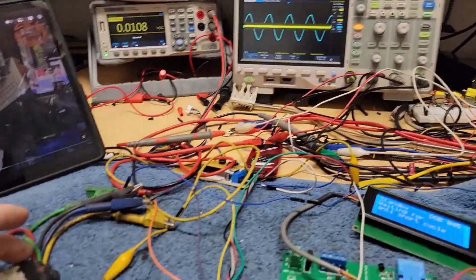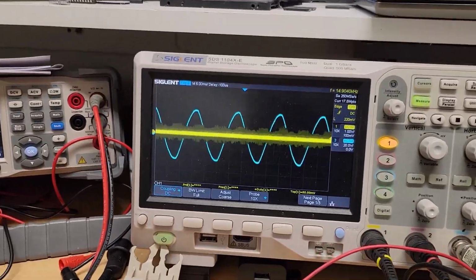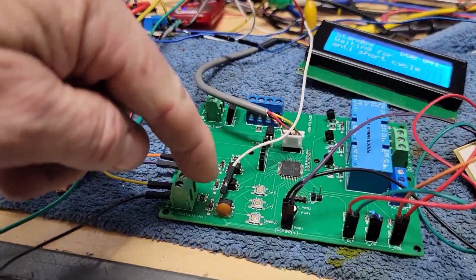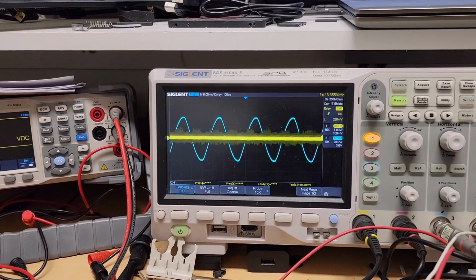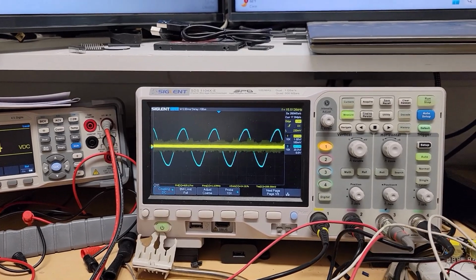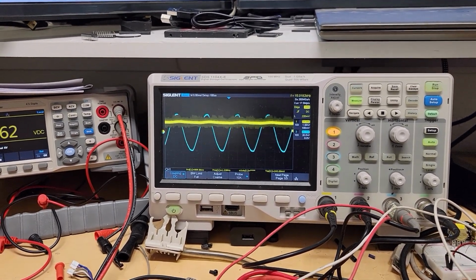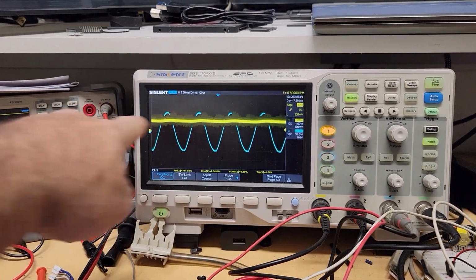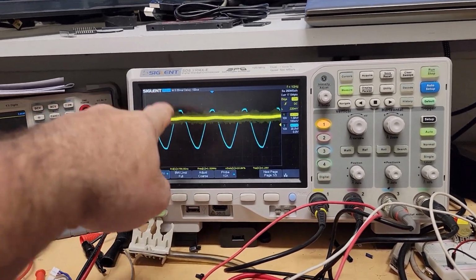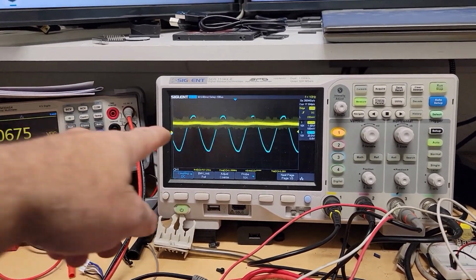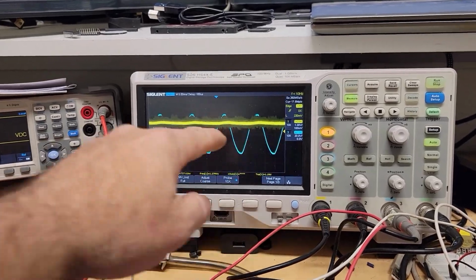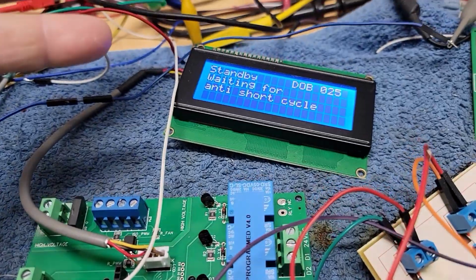Alright, got it ready to go. Reversing valve's on, so we're looking at that AC input over here, but now we're checking Y1 at the optical isolator. Should be a smooth transition with the yellow going up. There it goes—no more rectified pulses that weren't being filtered out like we just saw a second ago.